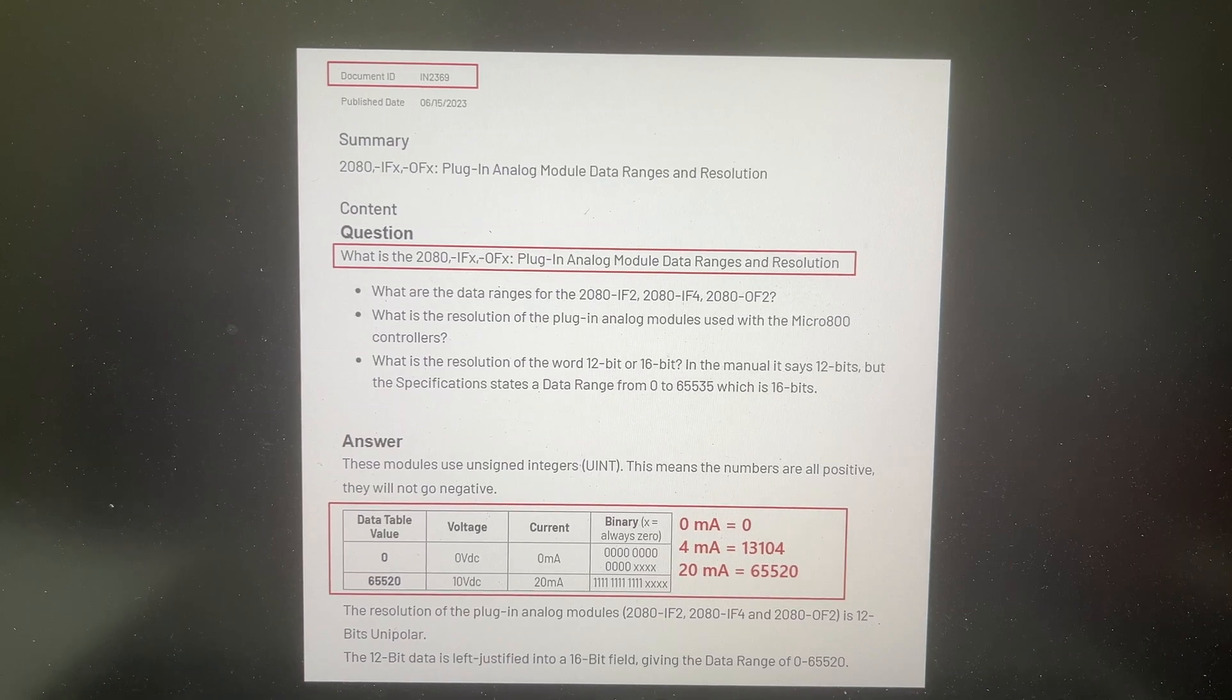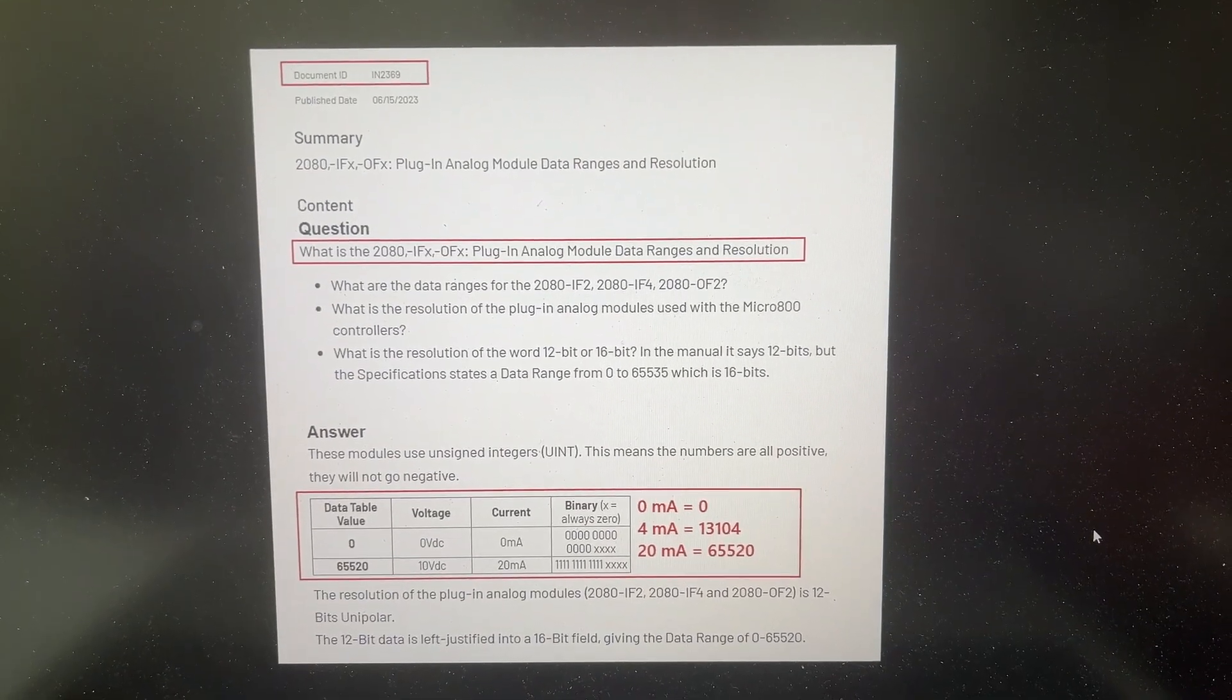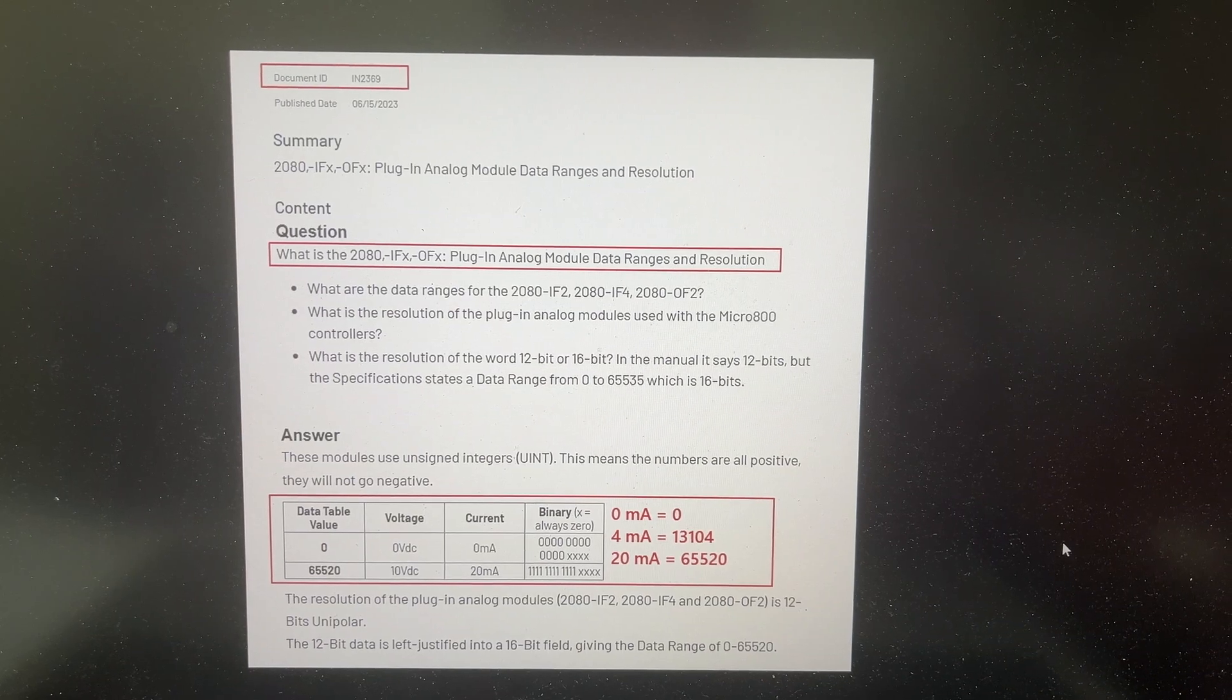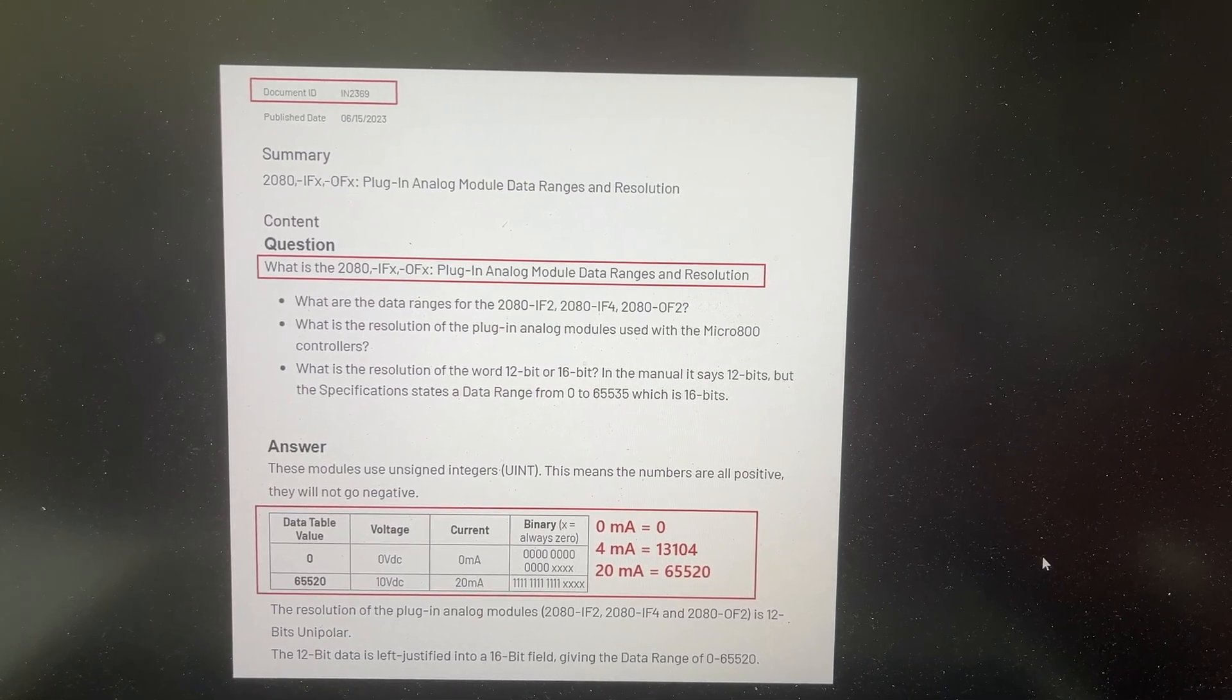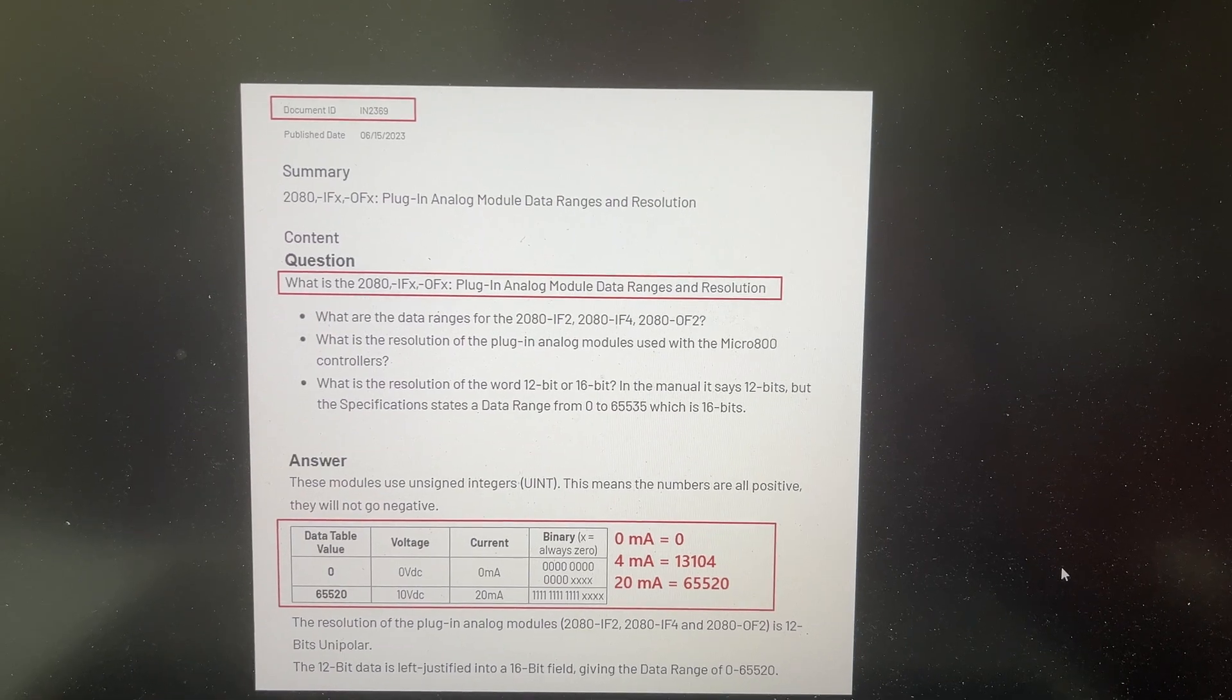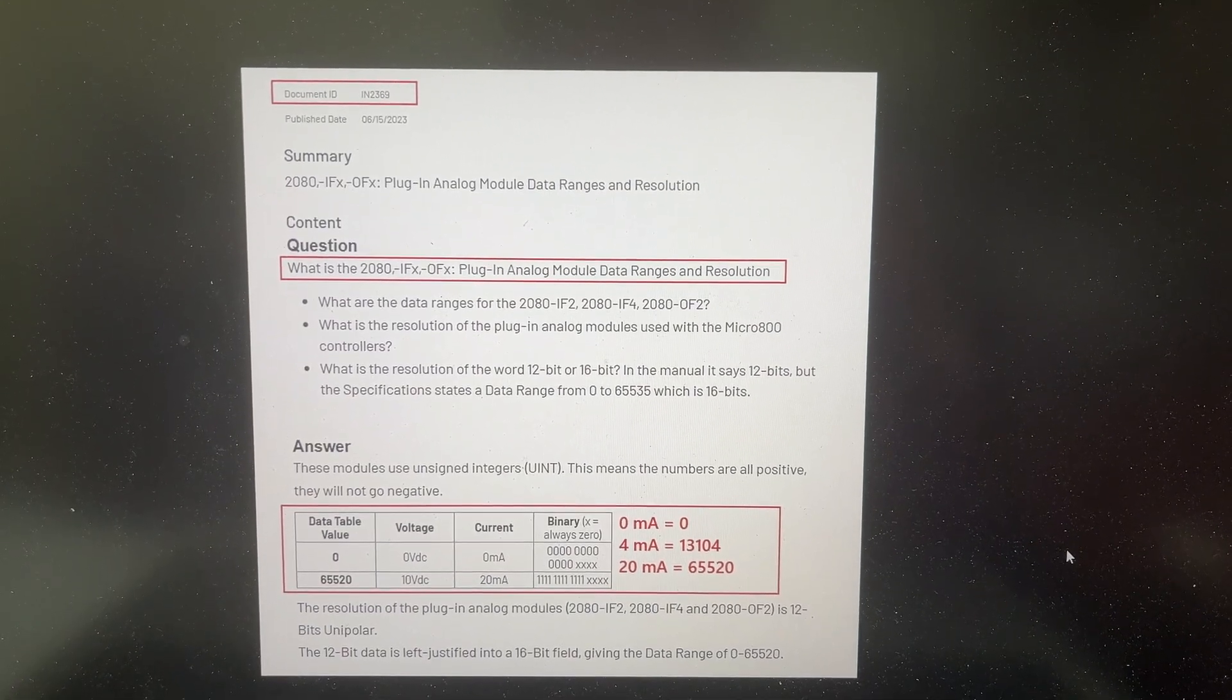This document is from Rockwell Automation Knowledge Base Center. For all plug-in analog input and output modules, the range for the PLC tags for all 0 to 10-volt signals or 0 to 20 milliamp signals is 0 to 65,520. If the signal is 4 milliamp, the PLC tag value will be 13,104.